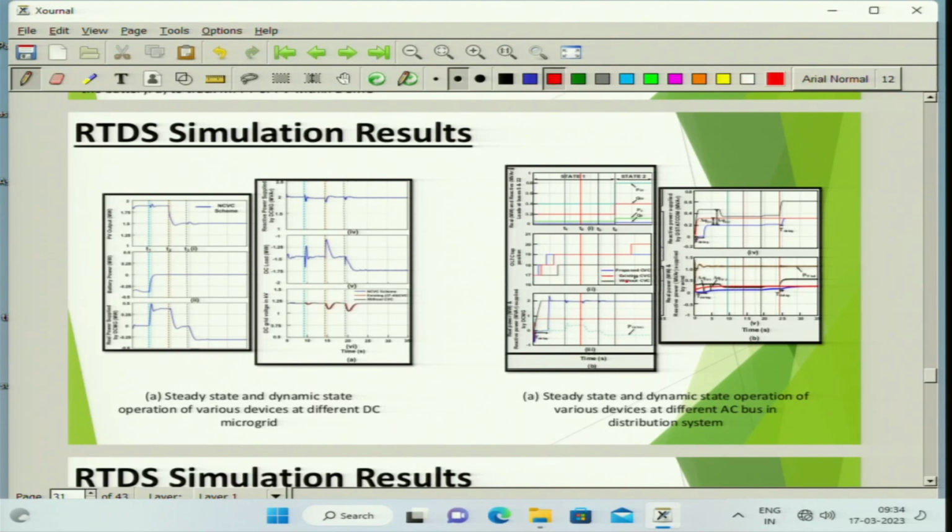So, we have compared with the existing scheme, which I have already discussed, where they consider steady state and dynamic state. During steady state and dynamic state, all the voltage regulating devices, OLTC and fast acting converters, play a master role, whereas in our case we are not allowing fast acting converters to play a master role. And then there is the without CVC scheme, that means haphazardly everybody is acting, there is no intelligent control monitoring any of these devices. All the voltage regulating devices are acting on their own.